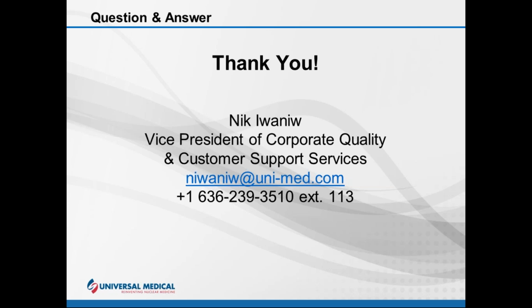And what I advise, and this is real important for the engineers out there working with the technologists in nuclear medicine, is that when ACR accreditation is coming in, ACR is really strong on image quality. They do a SPECT phantom if you're doing SPECT. Image quality in floods, bar phantoms, resolution is real important. I strongly encourage that when we know the ACR accreditation is scheduled, the engineers come in and do a complete tune on the camera, so that it is performing pristinely as far as resolution and uniformity. That way, when we submit our images to the ACR, we have a high likelihood that we're going to pass with no problem.